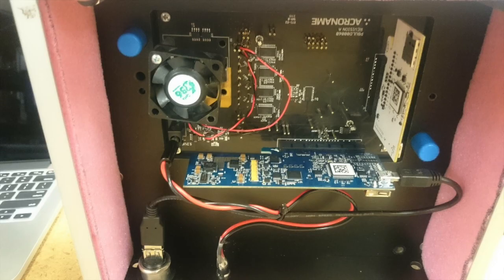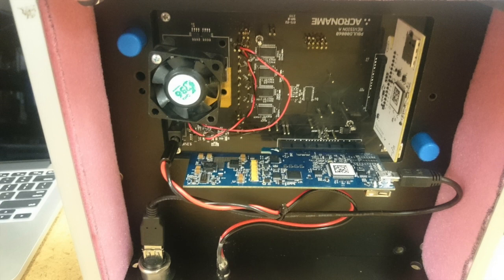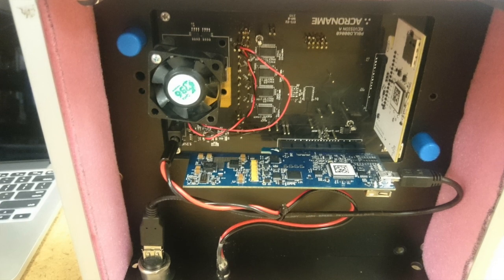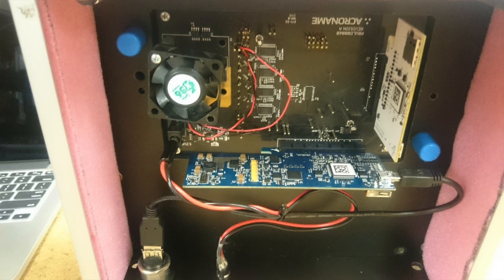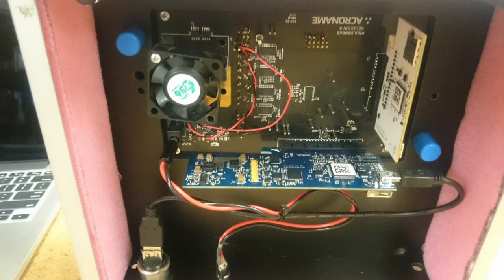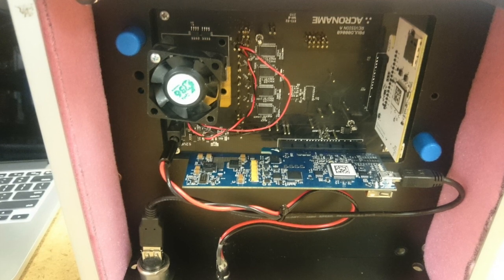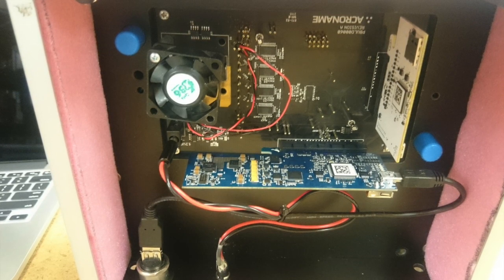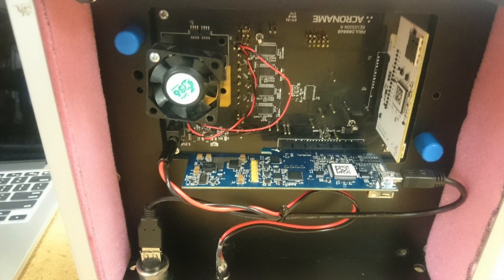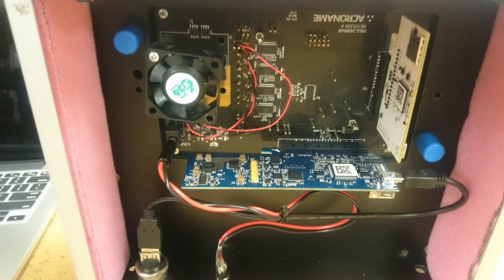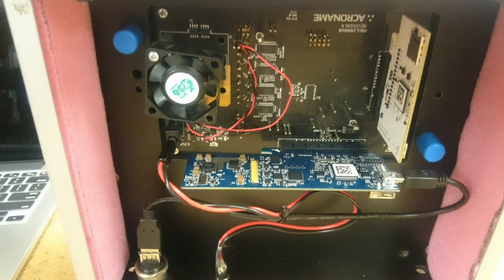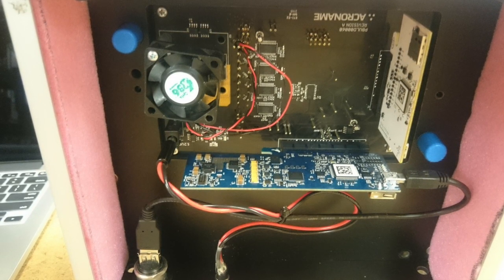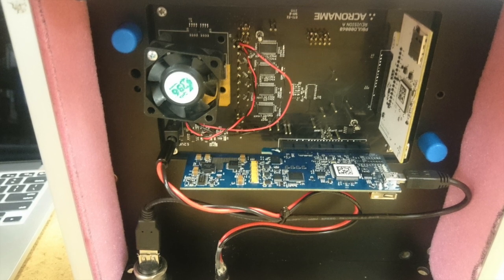Tipping the fixture up, you can see how elegant the fixture internals are. Since MTM modules are networked through Acroname's brainstem technology, just one data connection to one of the MTM modules is all that's needed, and now the test host can access all the MTM modules in the tester.